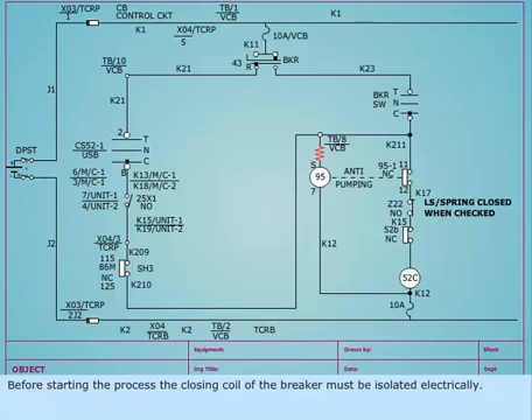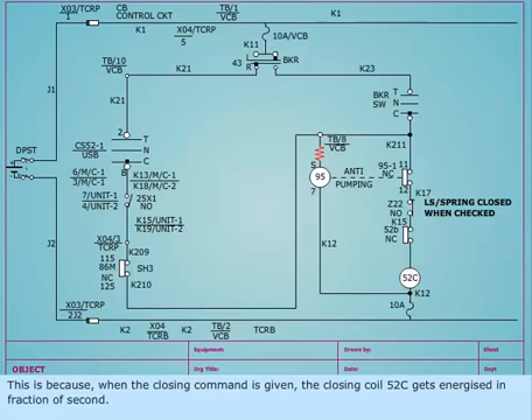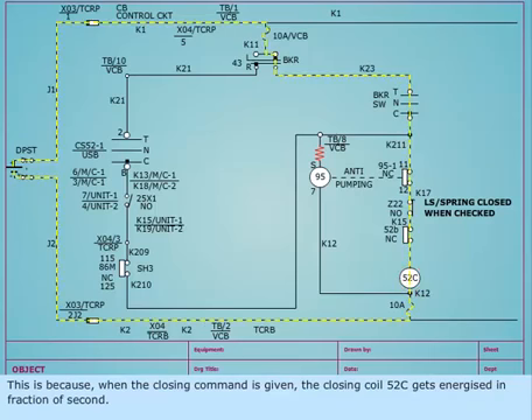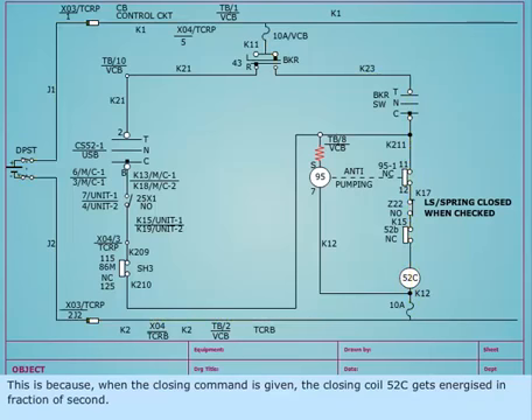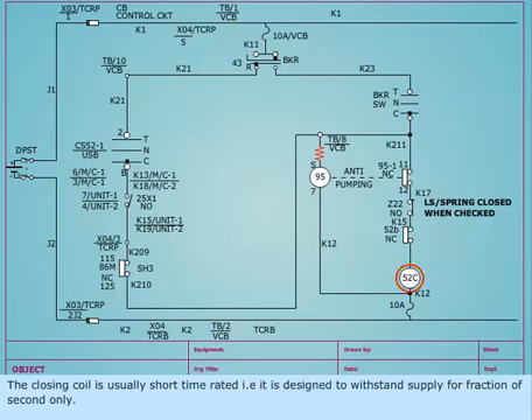Before starting the process, the closing coil of the breaker must be isolated electrically. This is because when the closing command is given, the closing coil 52C gets energized in fraction of a second. The closing coil is usually short time rated, that is, it is designed to withstand supply for fraction of a second only.